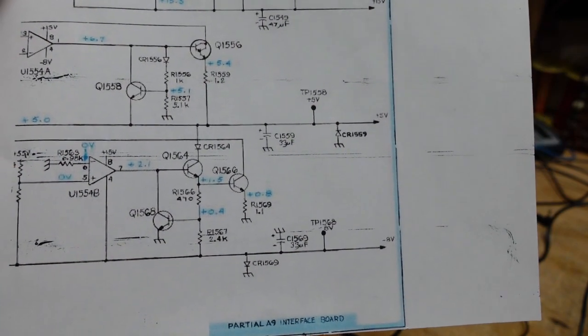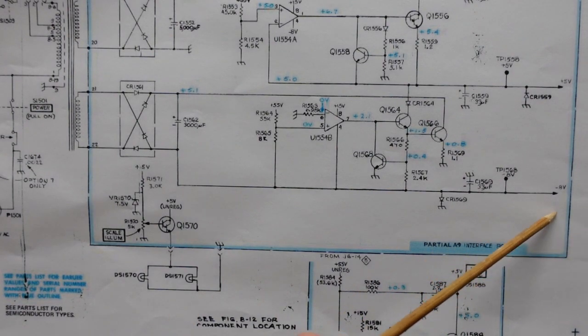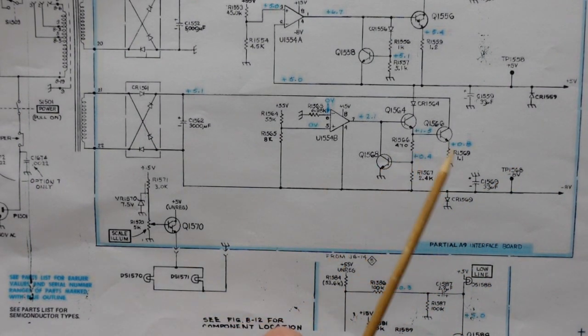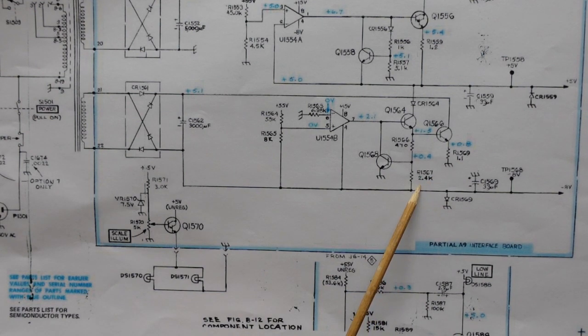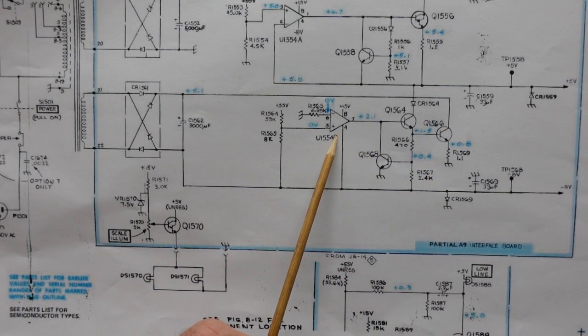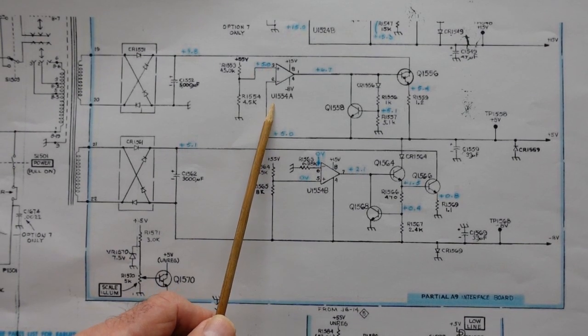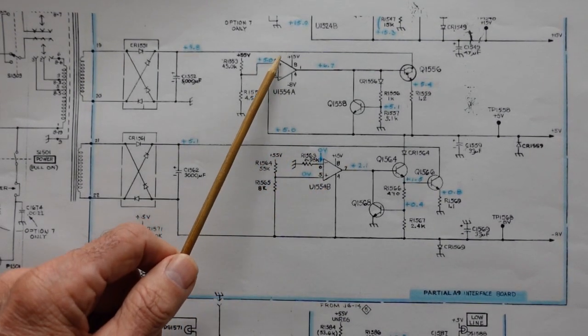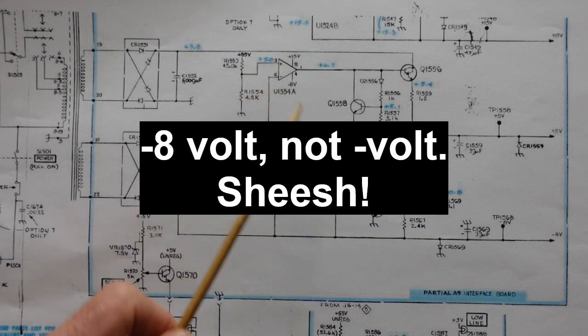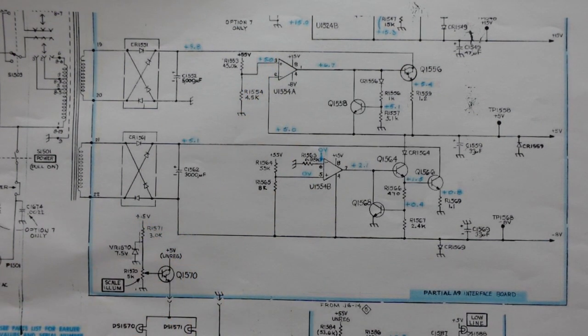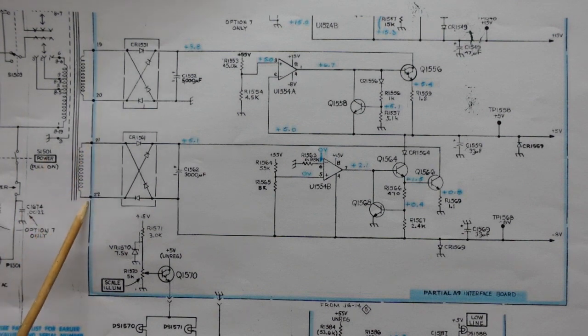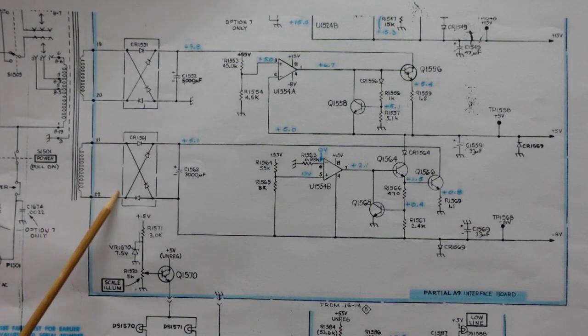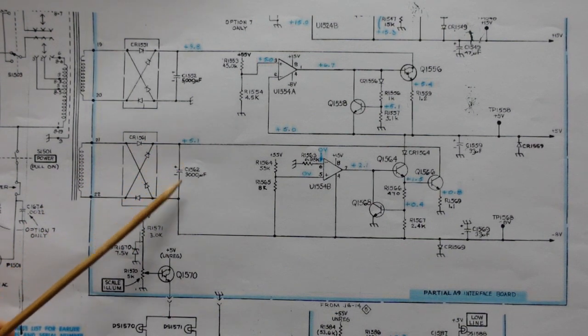Okay, I spent a little bit of time trying to figure out what's going on with this 8 volt supply that's comprised of these elements right here. I don't see anything wrong with the 8 volt supply. However, this is interesting because without the 8 volt supply we lose power to this op amp. If you take a look up here, this is U1554A and B, it's a dual op amp and its power supplies are fed by our positive 15 and our negative 8 volt. Without our negative 8 volt, this op amp will not operate correctly. So it's kind of a chicken and egg problem, but I believe that the problem is actually back here somewhere. I can't get to these, or at least I don't know how to get to them from the side of the board that's exposed. This bridge rectifier I can't get to either, but I'm not getting good voltage here.